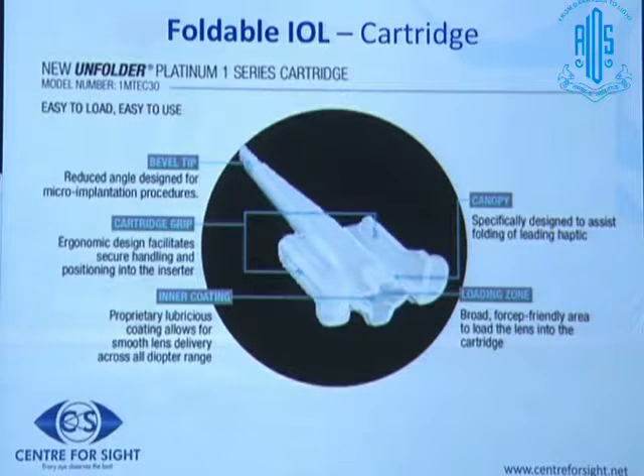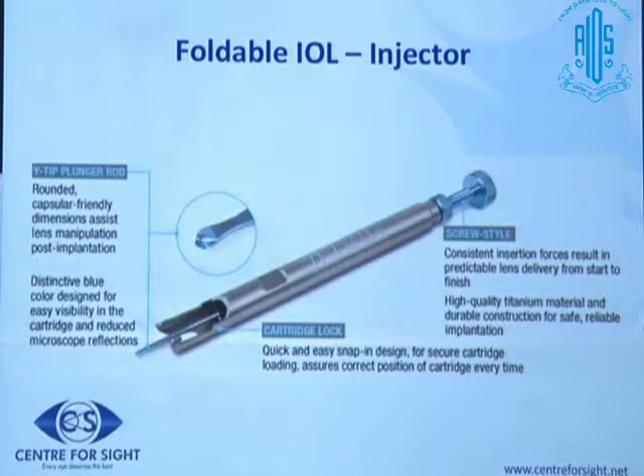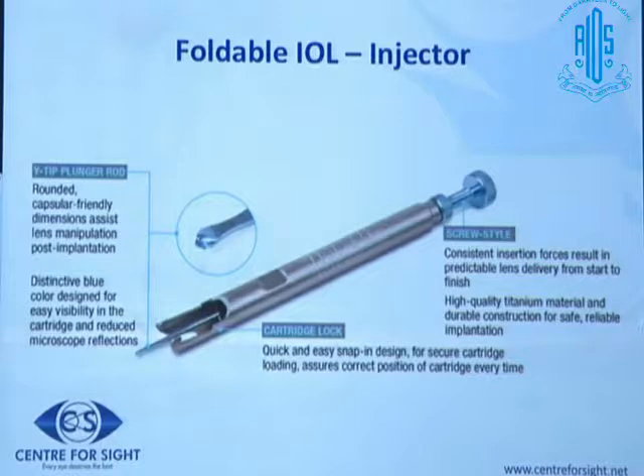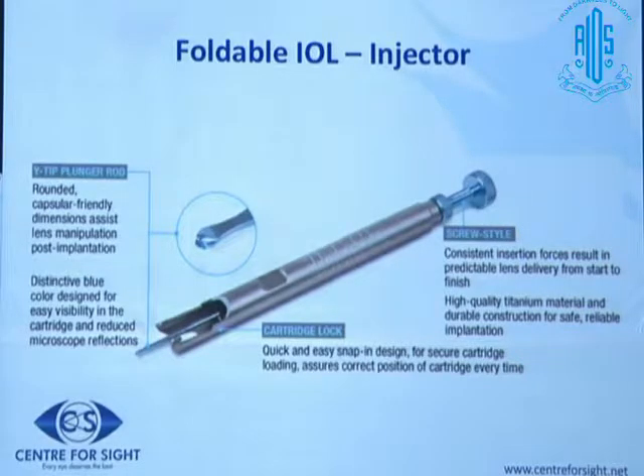The cartridge is fitted onto the injector, the intraocular lens is loaded into the cartridge, and the push plunger advances the lens. There are two types of injector systems: a push type and a screw type. The screw type is preferable because you don't get sudden violent jerks — with the push type, if there is resistance and you push hard, you could forcefully displace the IOL, as has been seen at conferences.